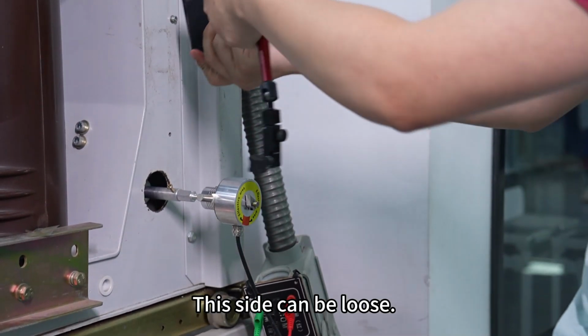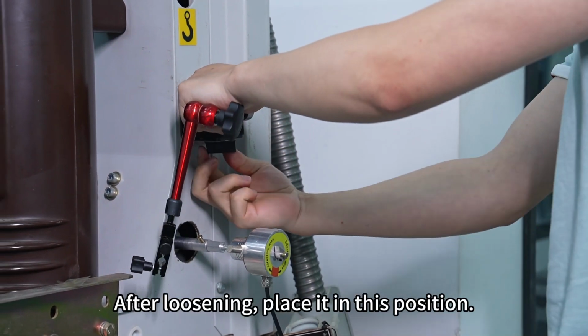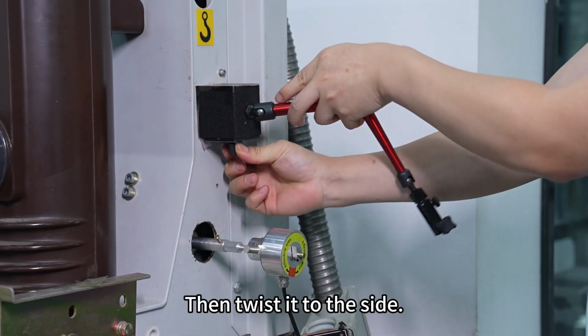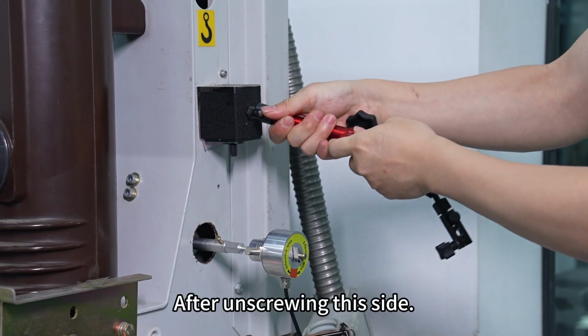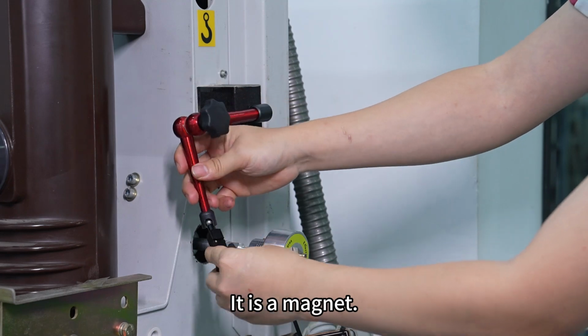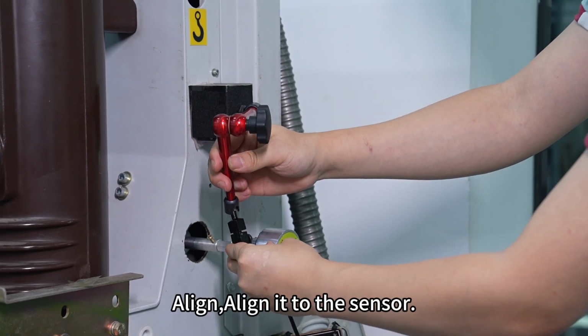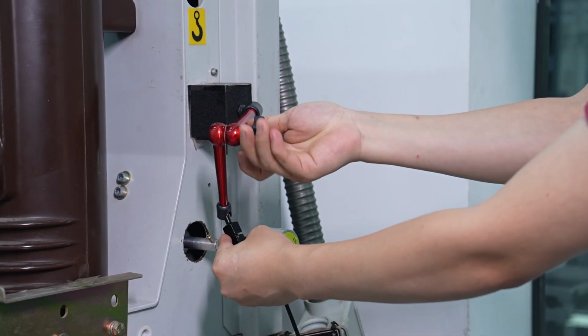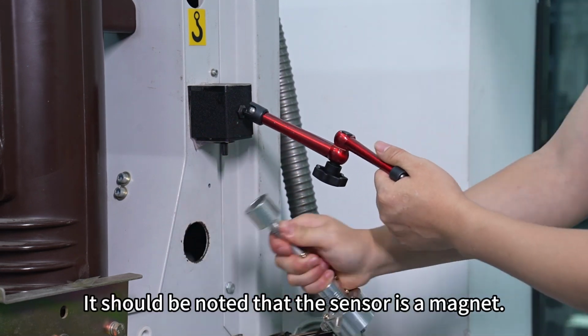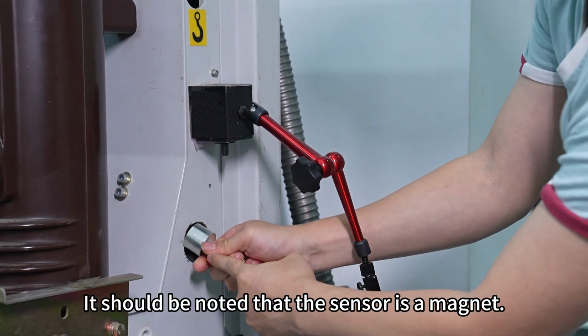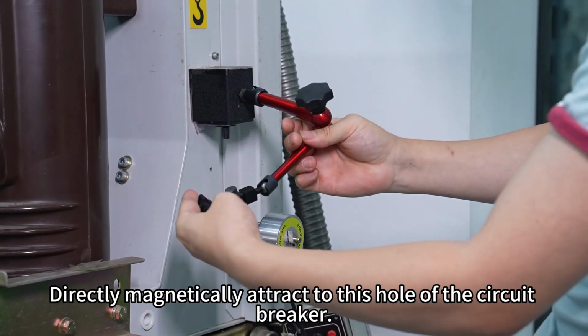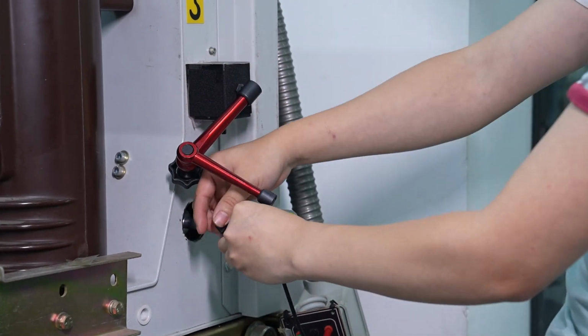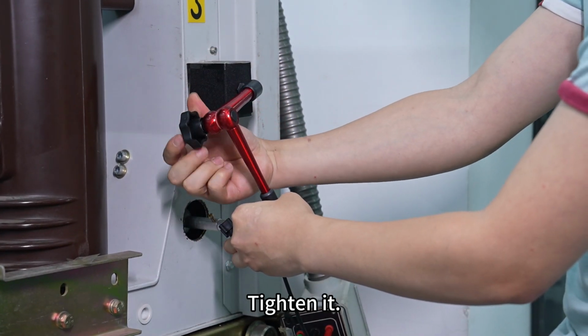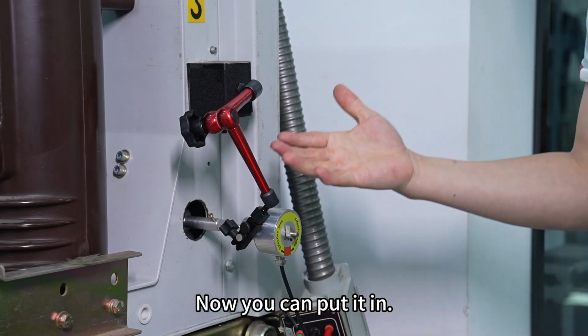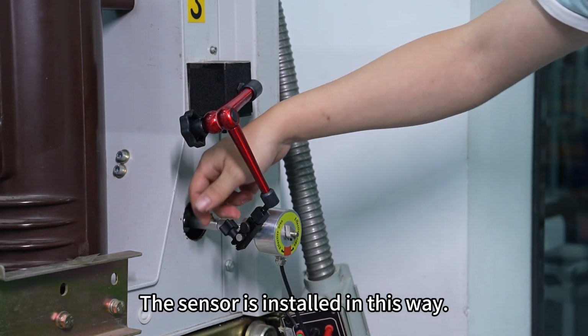This is a magnetic suction seat. This side can be loosened. After loosening, place it in this position. Then twist it to the side. After unscrewing this side, it is a magnet. It attracts it. Align it to the sensor. Just tighten it. It should be noted that the sensor is a magnet. Directly magnetically attract it to this hole of the circuit breaker. After attracting it, tighten it. Now you can put it in. The sensor is installed in this way.